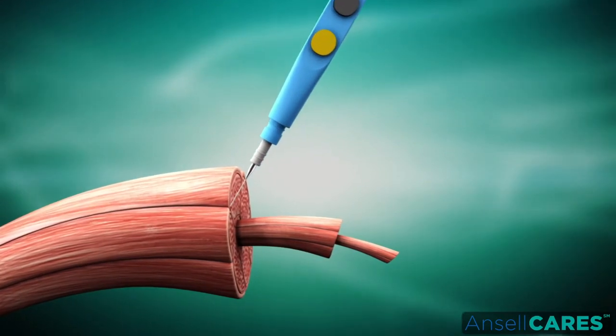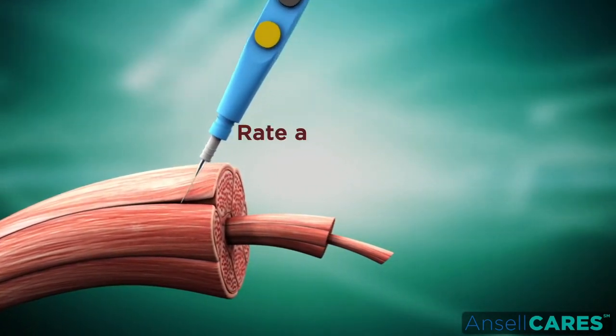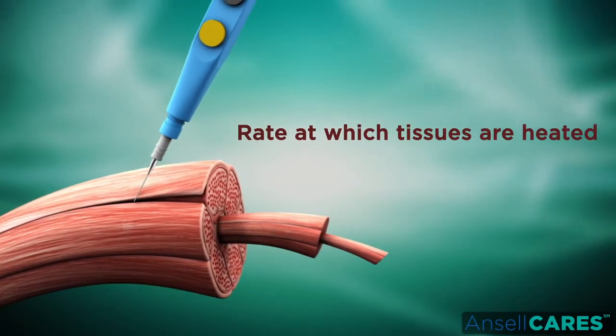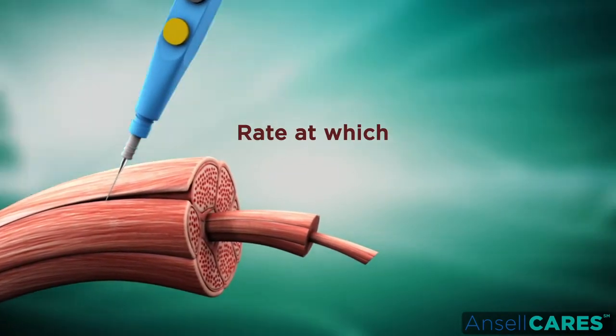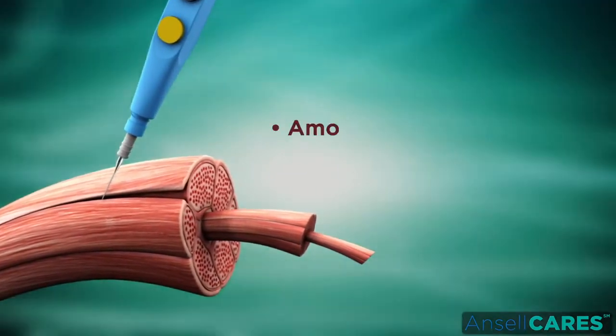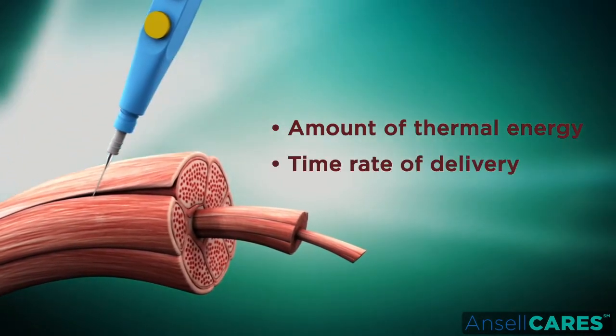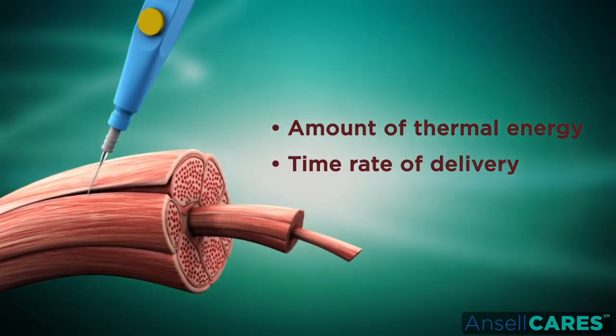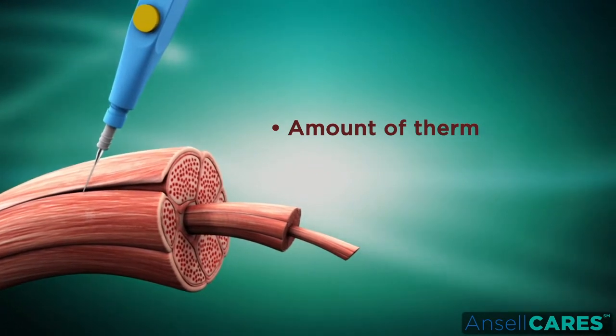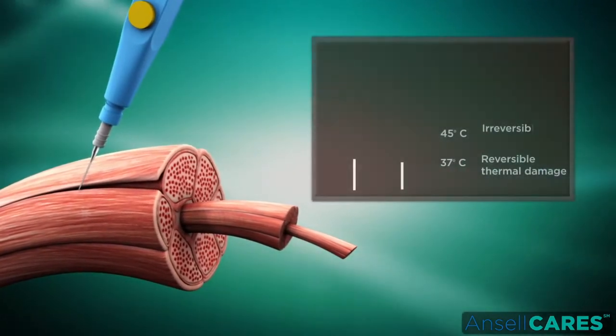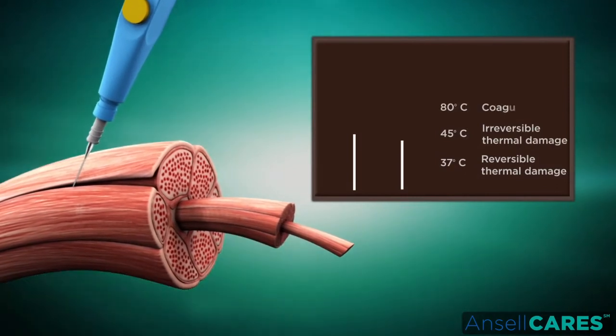The heating effects produced are central to the desired function of the electrosurgical instrument. The rate at which tissues are heated plays a crucial role in determining clinical effect. The amount of thermal energy delivered and the time rate of delivery will dictate the observed tissue effects. In general, below 45 degrees Celsius, thermal damage to tissue is reversible.